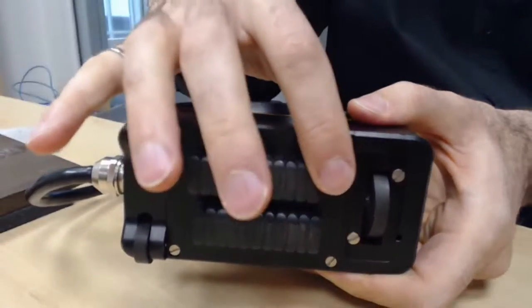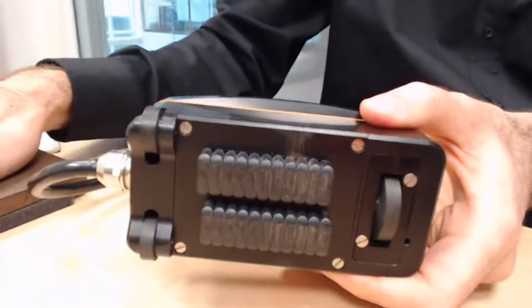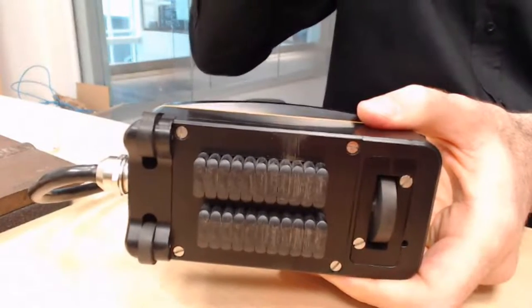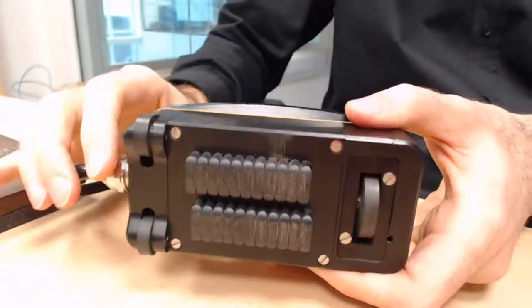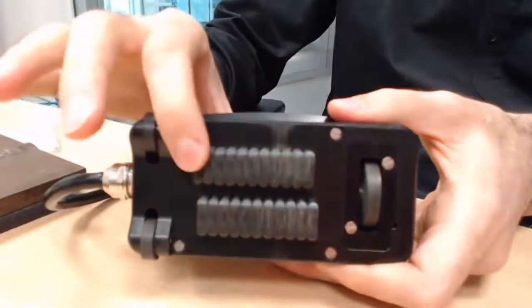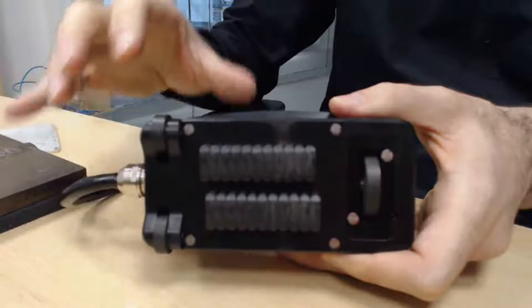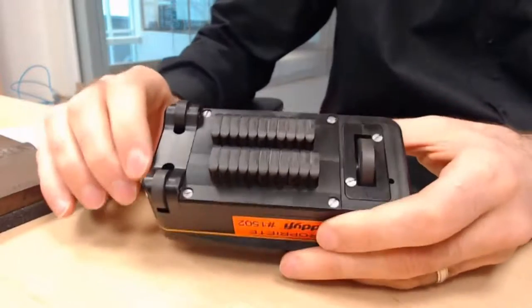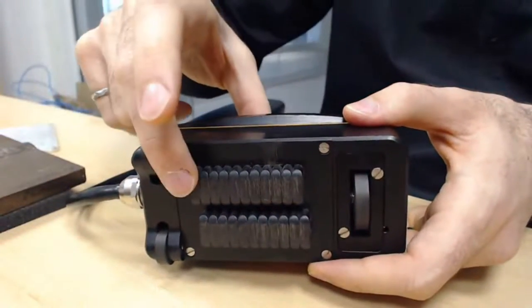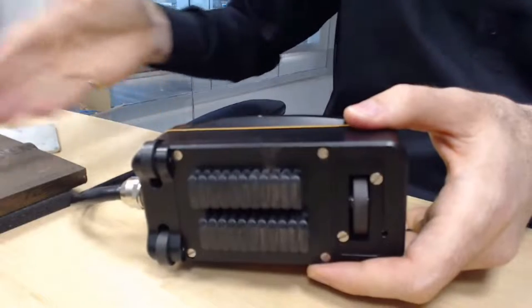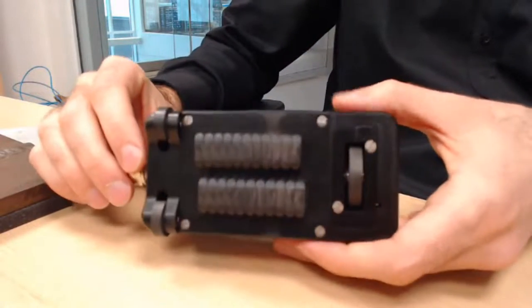Those sensors are made of ceramic, so they are extremely resistant to abrasion to wear. We've been using ceramic now for four years, about half the lifetime of the Shark. We really never heard about a ceramic finger getting worn out completely. It takes a really long time to go through ceramic material when inspecting carbon steel, which is good because if those fingers were made of plastic, it would go through the plastic much faster.